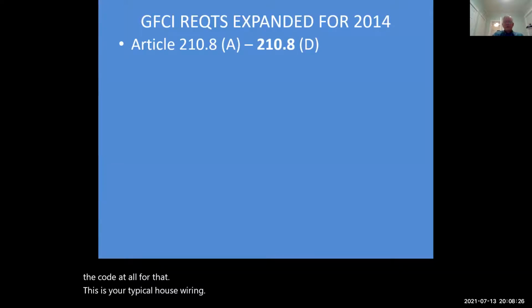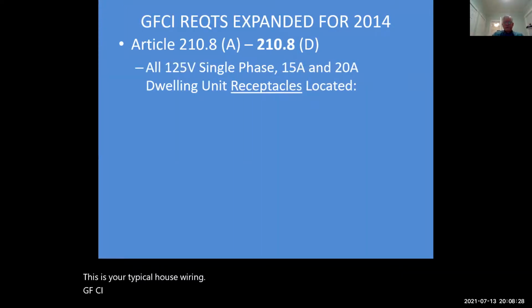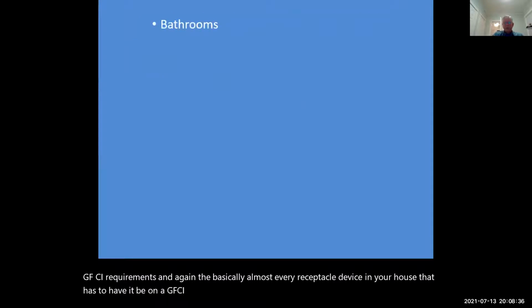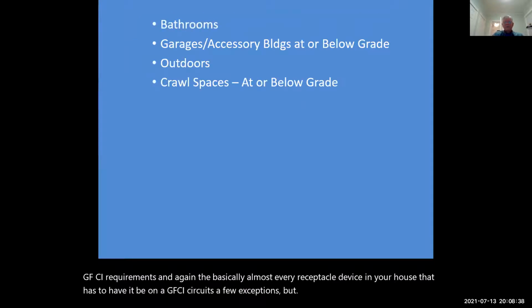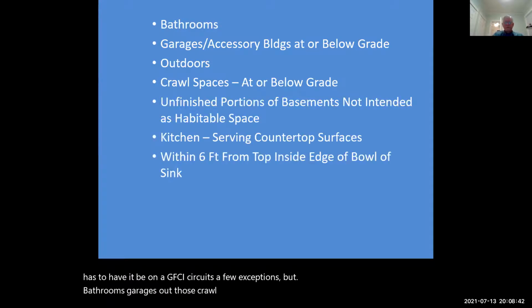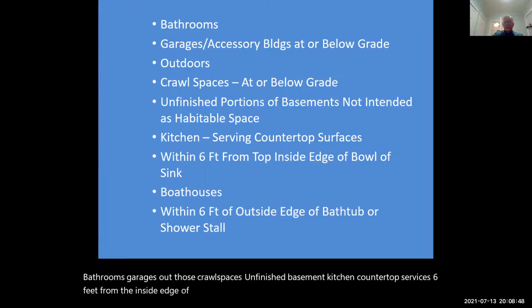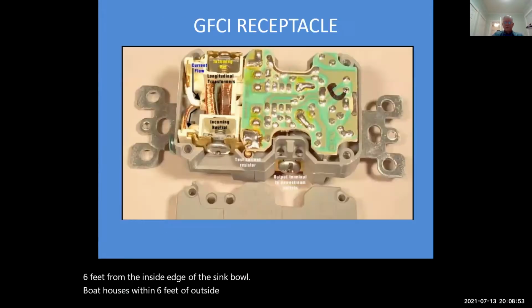GFCI requirements, and again, almost every receptacle device in your house now has to be on a GFCI circuit. There's a few exceptions, but bathrooms, garages, outdoors, crawl spaces, unfinished basements, kitchen countertop surfaces, 6 feet from the inside edge of the sink bowl, boat houses, within 6 feet of the outside edge of a bathtub or shower stall, laundry areas.